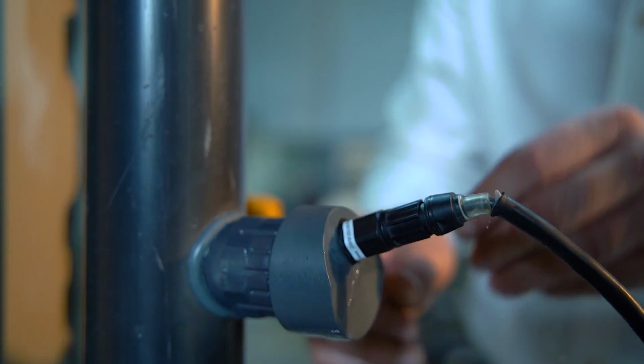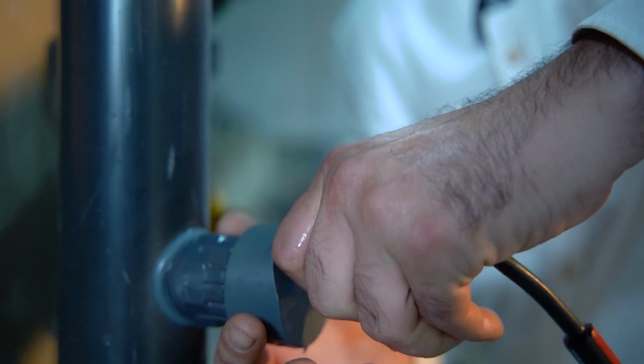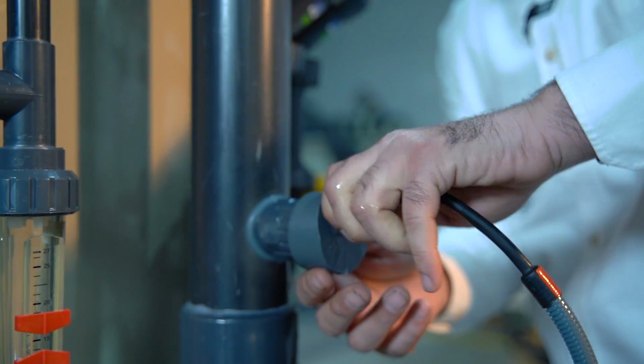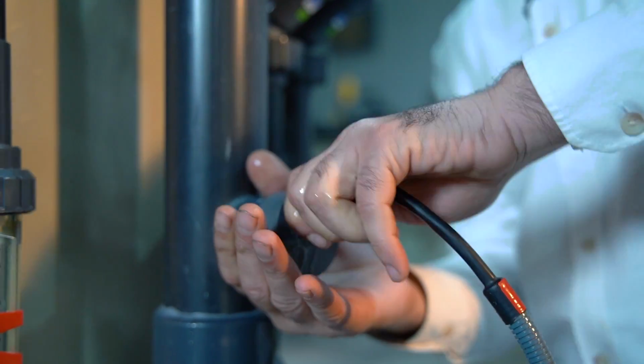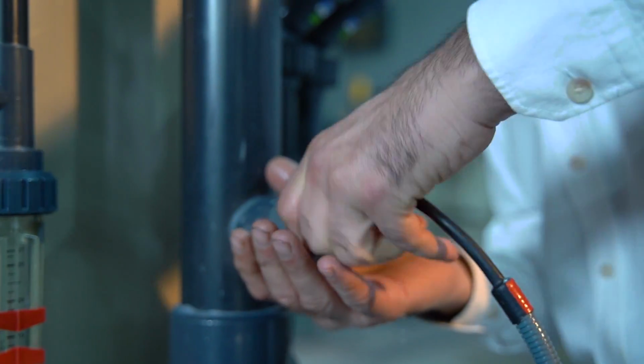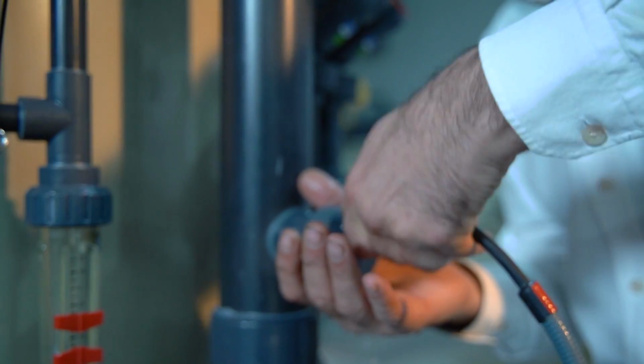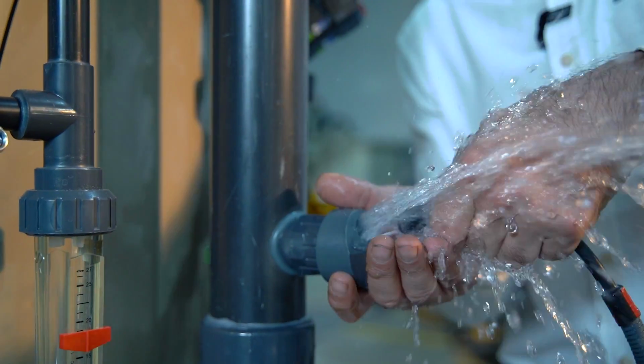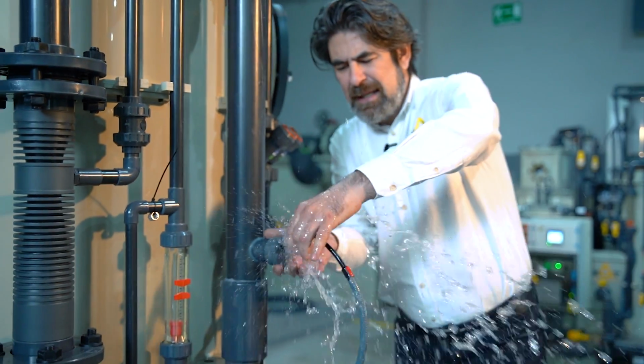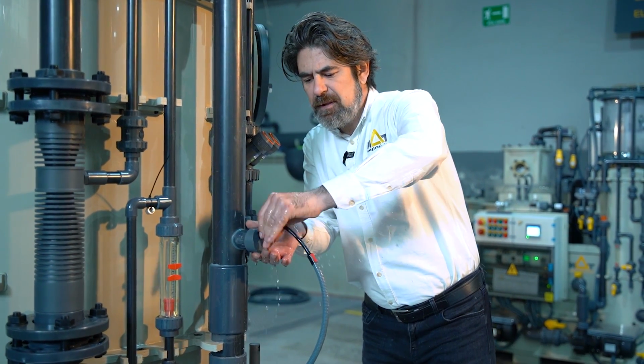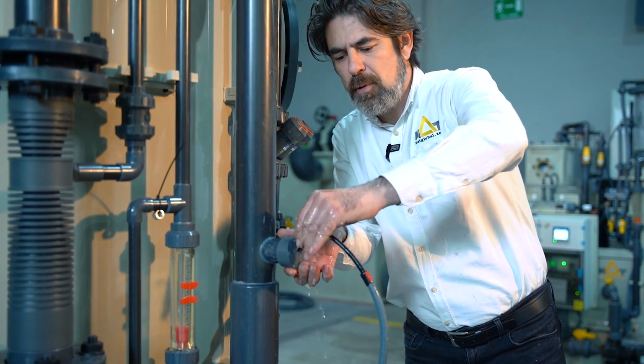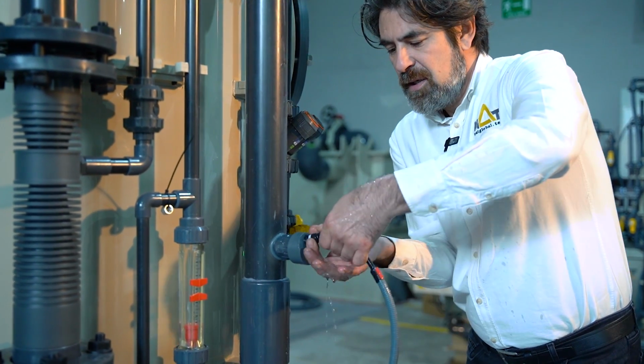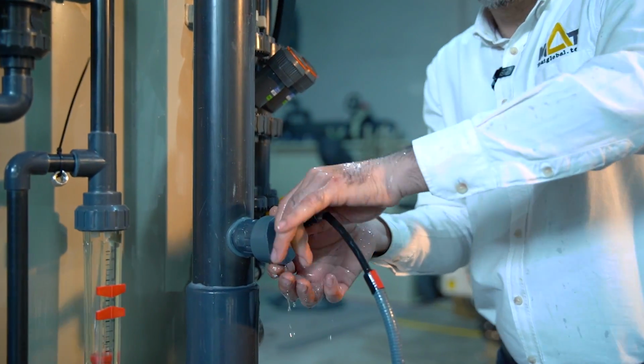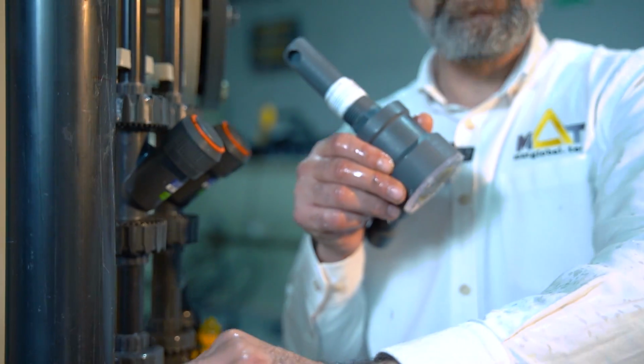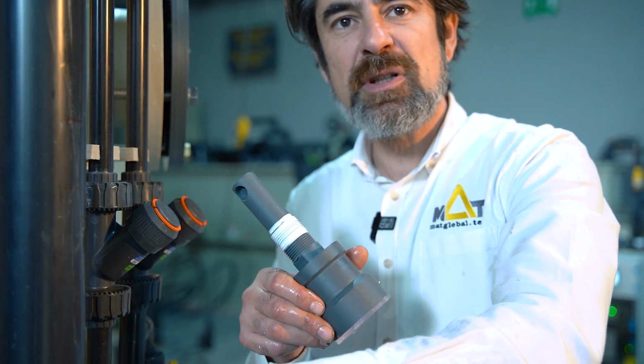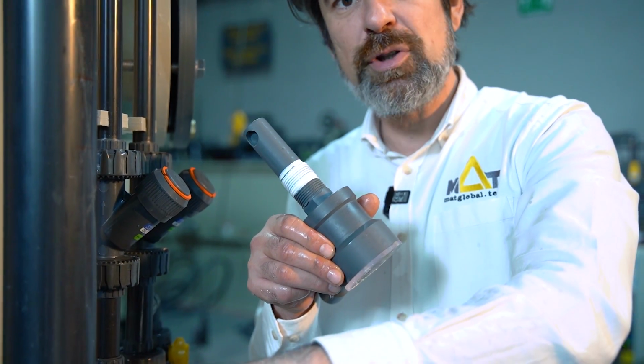So if I want to service the probe, and if I want to remove the probe while there is a flow inside the pipeline, this is the result. It's almost impossible to change or service the probe while there is water inside. So the solution of MAT for this is our dry tap application. Now I will insert this dry tap station into the pipeline and show you the difference.